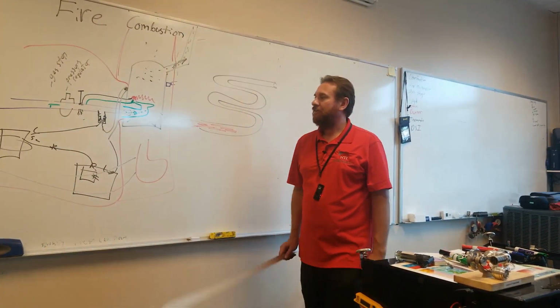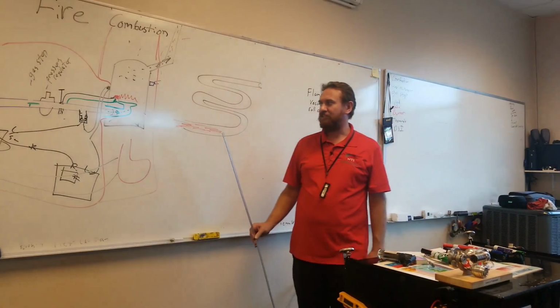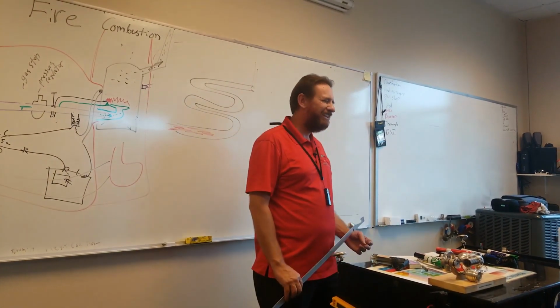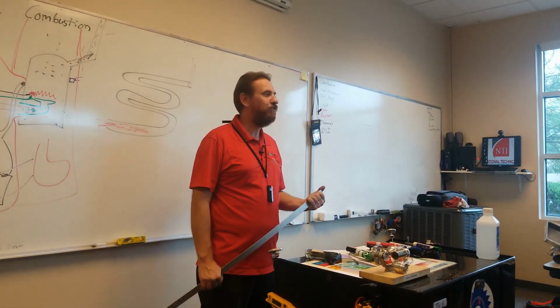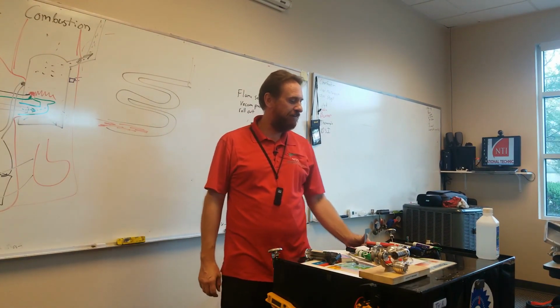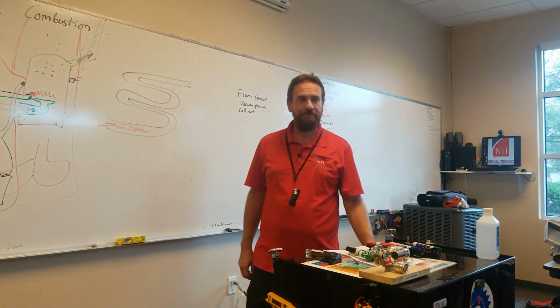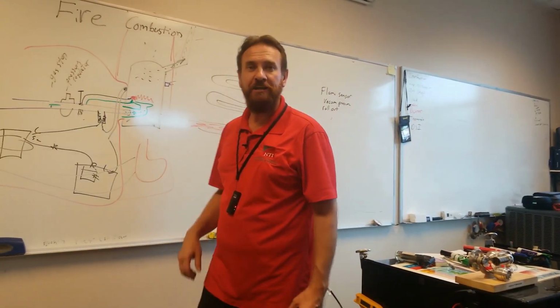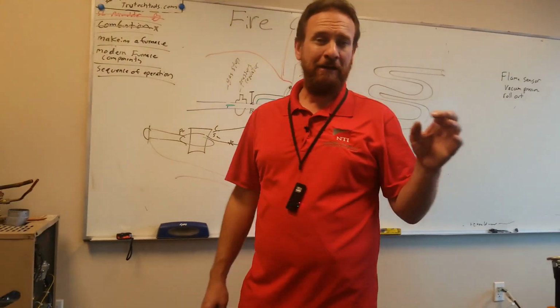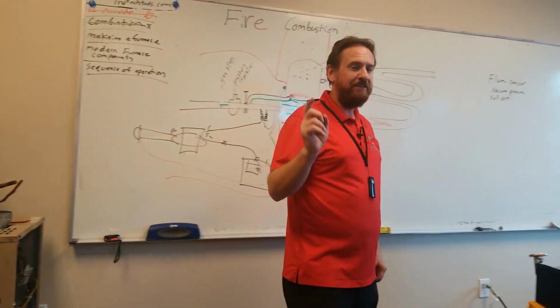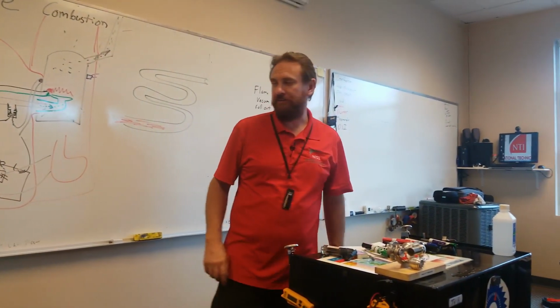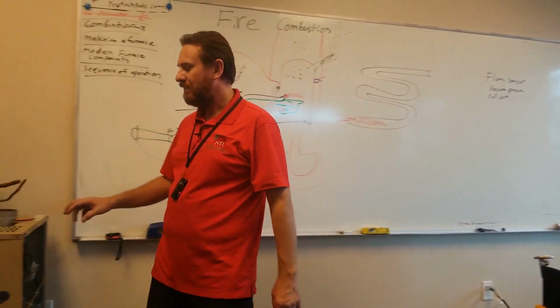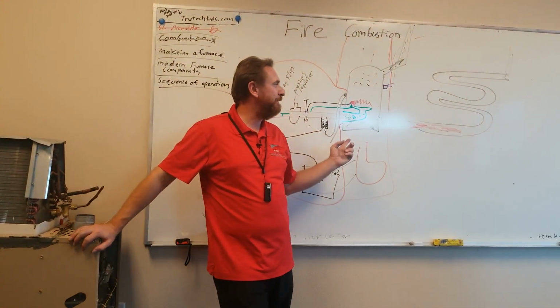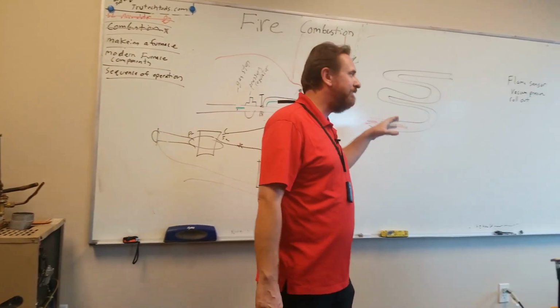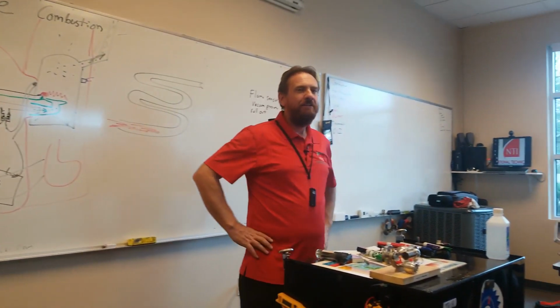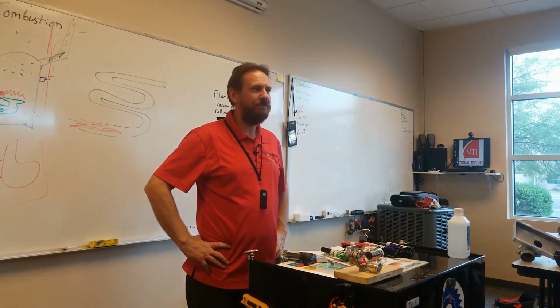Need to replace it. So the two types of ignitions we have are direct spark ignition and hot surface igniter. Those are the two that we're going to focus on. We're going to focus on flame sensors instead of thermocouples. Before we get into all this other stuff, we've covered a lot of components. I want you guys to take your notebooks and go out to the lab, look at those furnaces. Look at these gas furnaces and start thinking about all the stuff we talked about. See if you can simply identify some of the parts we've talked about. See if you can look at that furnace and see how it's working.